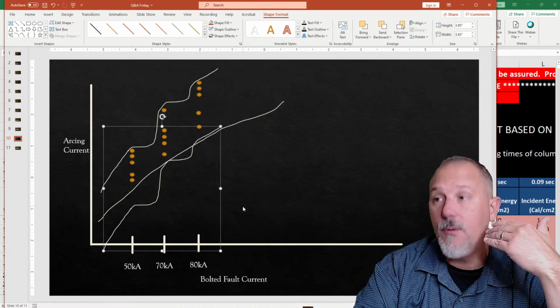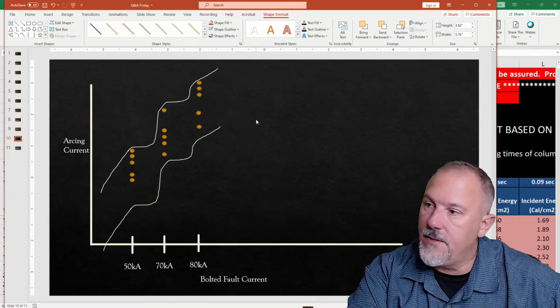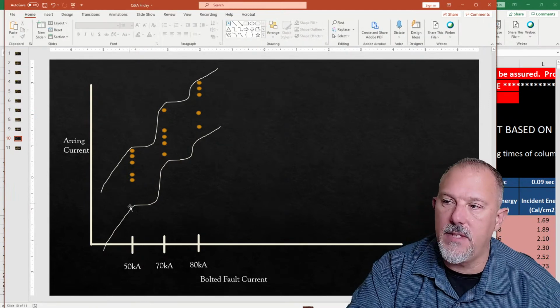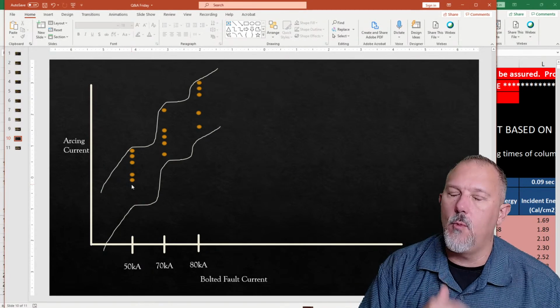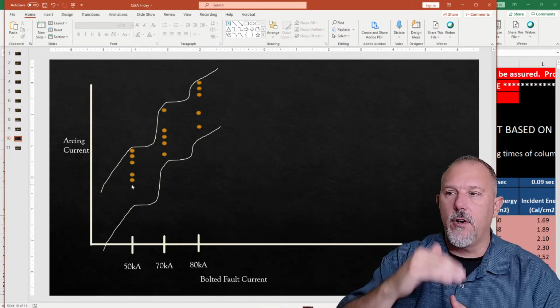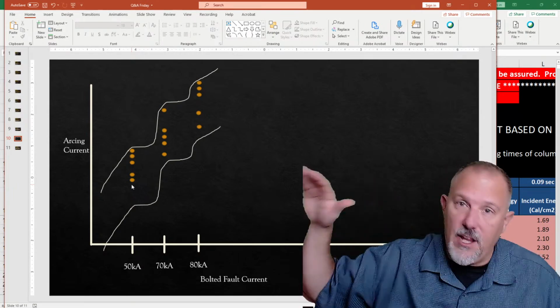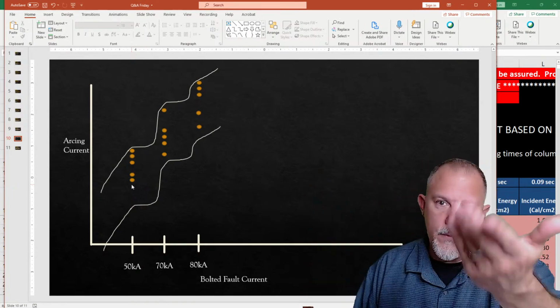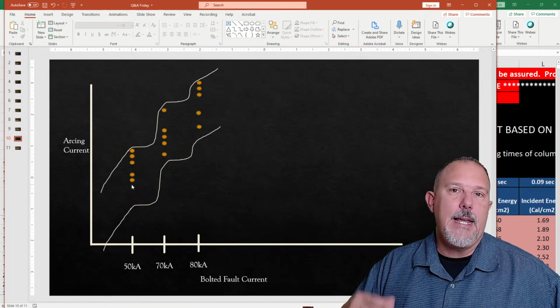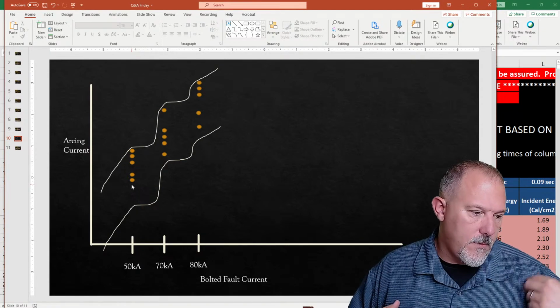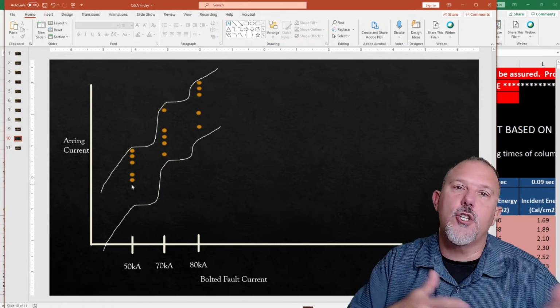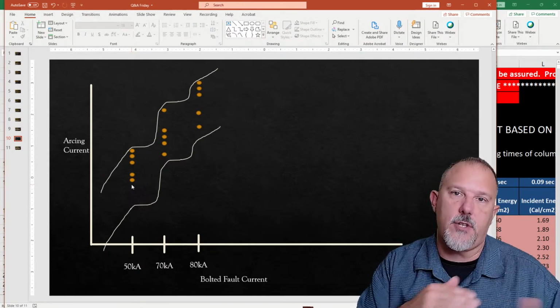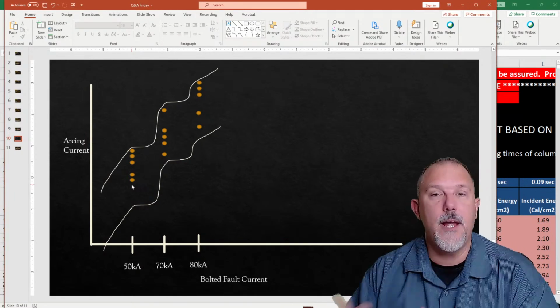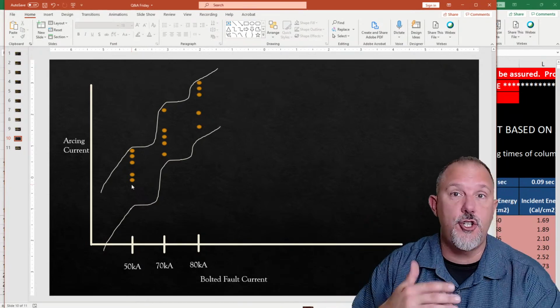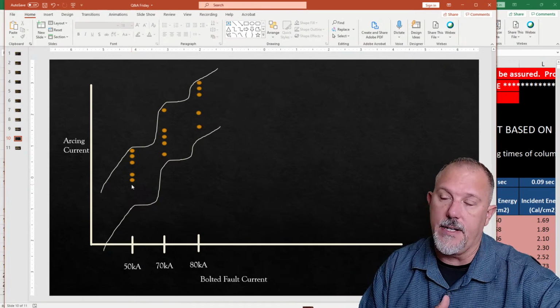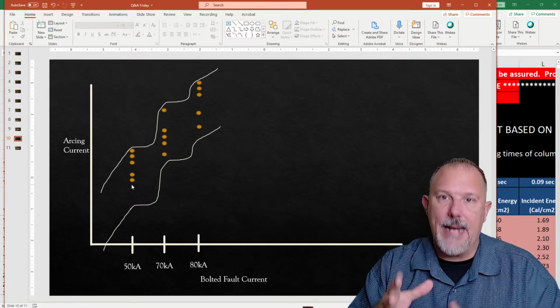And what he would even tell you is that when he took the 85%, there were some data points where the arcing current was much lower than what it had to be, because he didn't get any values of arcing current that low. But because he was just doing 85% to make it easy, I think it was JW's point, the arcing current that you would calculate at 85% was much lower than what it actually was. And what does that do? That drives your incident energy up, right? Because you could be in a longer clearing time of your overcurrent protective device. So he tried to make that portion of the equation easy.